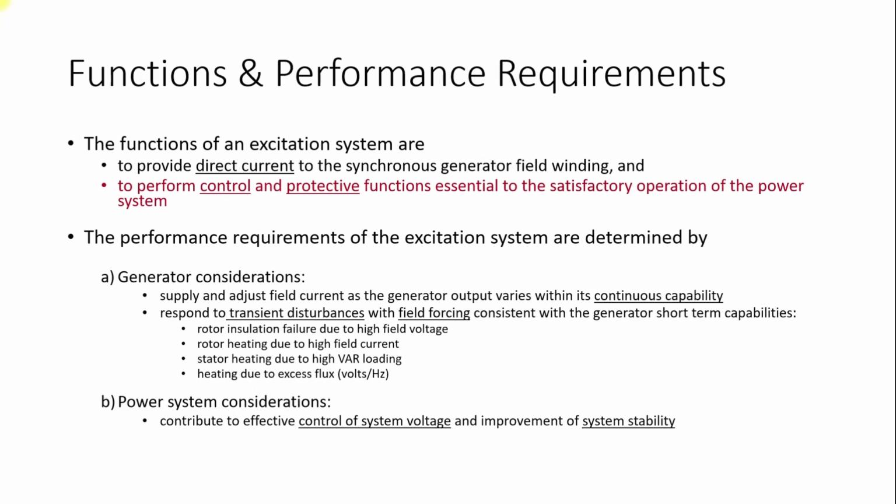That was the steady state operation. In steady state operation, if you see that the voltages are decreasing on the terminal voltage, what you will do is increase the flux in the system. This increase in flux increases the induced EMF in the stator, and on the terminal voltage you get some higher value of voltage. This way you control the voltages in the steady state operating range.